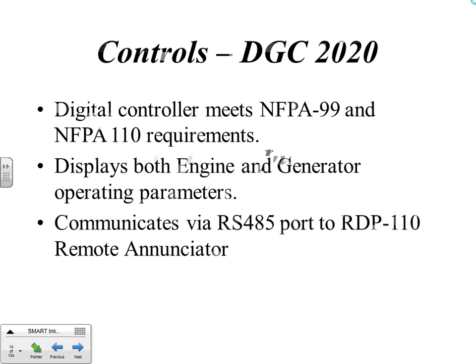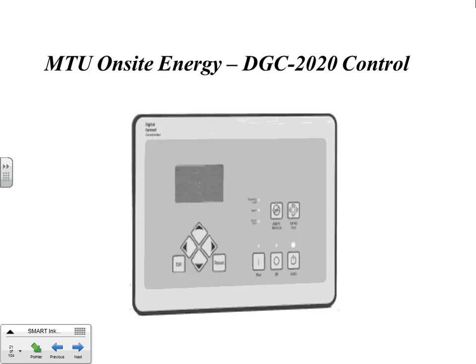On the control side, on our units, we have a digital controller that meets NFPA 99 and NFPA 110 requirements. It also displays all the engine and generator operating parameters, oil pressure, temp, and that kind of thing, plus voltage, current, and kilowatts. Also has communication port, and that's how it talks to the remote annunciator. This is what it looks like.